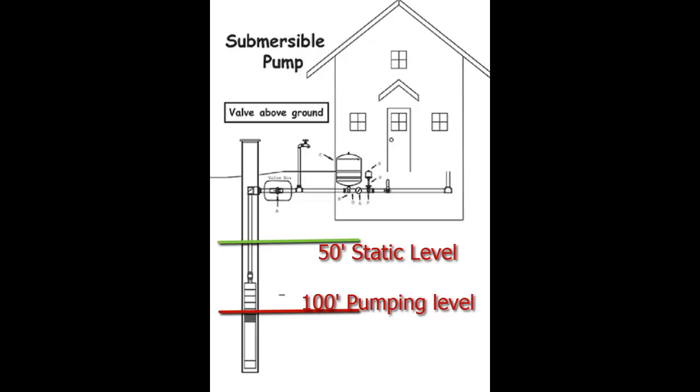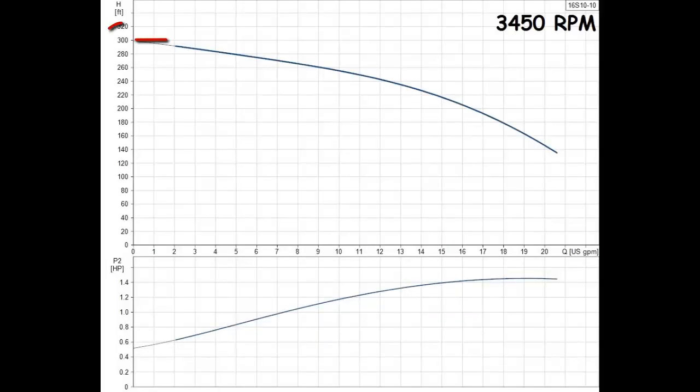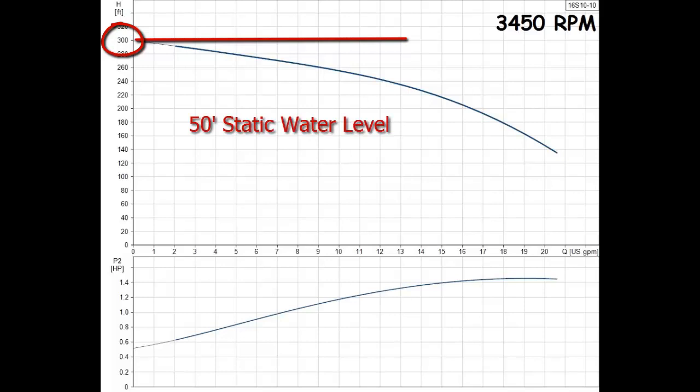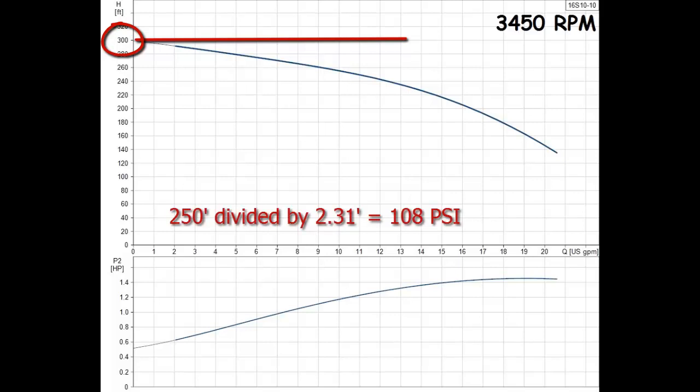Using the previous example of a well with a pumping depth of 100 feet, let's say the static water level measures 50 feet. Looking at the full speed curve at zero flow, this pump can build a total head of 300 feet. Since the static water level is 50 feet, we can deduct that from the 300 feet total the pump can build. 300 feet minus 50 feet equals 250 feet of head. 250 feet divided by 2.31 equals 108 PSI.